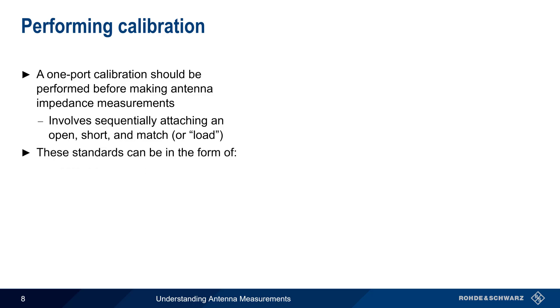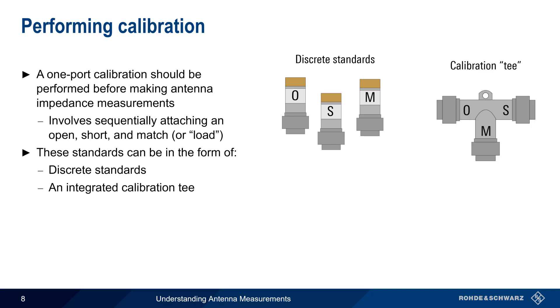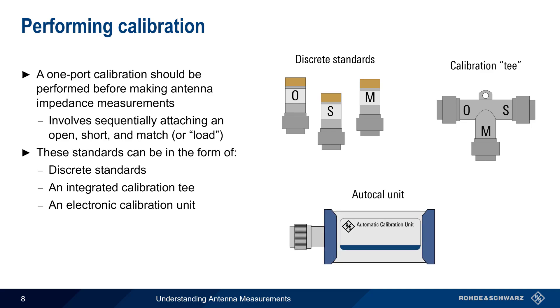These standards can be in the form of discrete standards, or they may be combined into a calibration tee. In addition to these manually attached standards, electronic calibration units can also be used. These units switch their internal standards in and out automatically, and are controlled by the attached VNA.